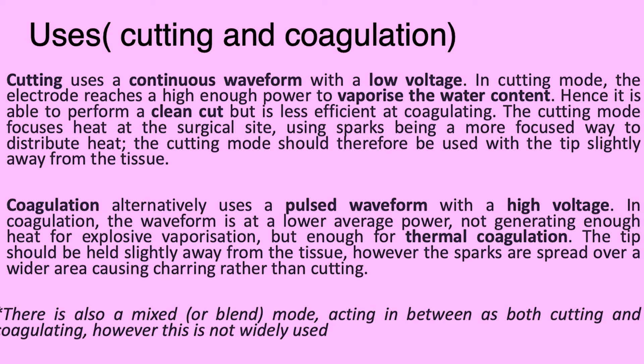Coagulation alternatively uses a pulsed waveform with high voltage. The waveform is at a lower average power, not generating enough heat for explosive vaporization but enough for thermal coagulation. The tip should be held slightly away from the tissue, but heat is spread over a wider area, causing charring rather than cutting. There is also a mixed or blend mode acting between cutting and coagulating, though it is not widely used.